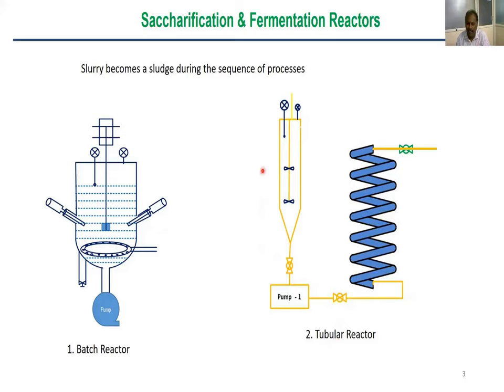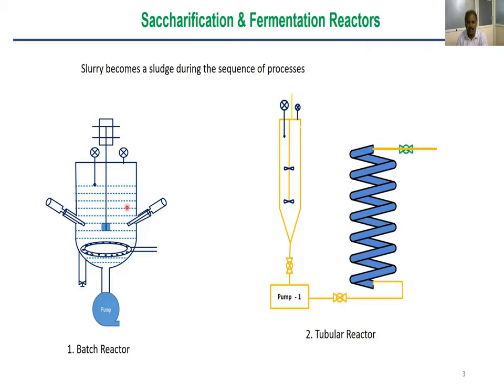For the tubular reactor, an impeller mixes the cellulose powder, biomass, water, and enzymes thoroughly, and then a pump supplies the slurry into the tube. Key design considerations include the distance from the bottom of the tank to the pump inlet — too long and conveying becomes difficult; too short and there may be space constraints for maintenance. We need to study how slurries move under impeller rotation and pump flow.